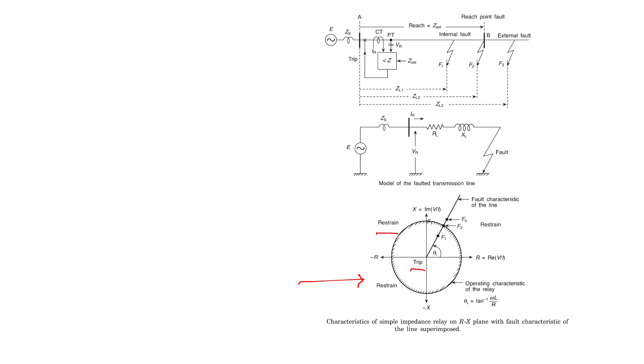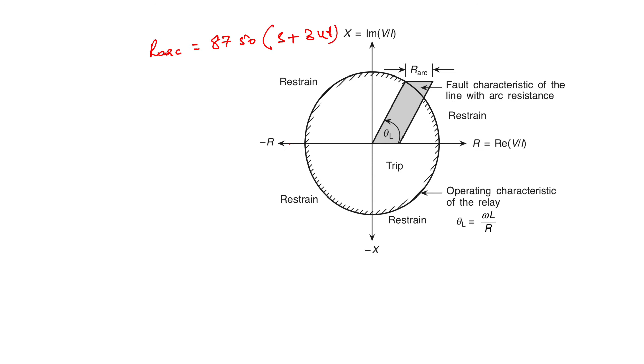Also, most of the faults involve arcing. The arc is resistive in nature. The arc resistance is a function of the spark over distance S, the wind velocity U, time T, and the current I in amperes. We discussed the Warrington formula for the arc resistance in the first chapter. The Warrington formula is R arc equals 8750 times (S plus 3UT) divided by I raised to the power 1.4. In this case, S is the spark over distance in feet, U is the wind velocity, T is time in seconds, and I is the current in amperes.